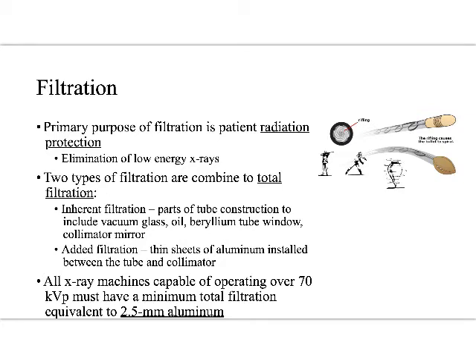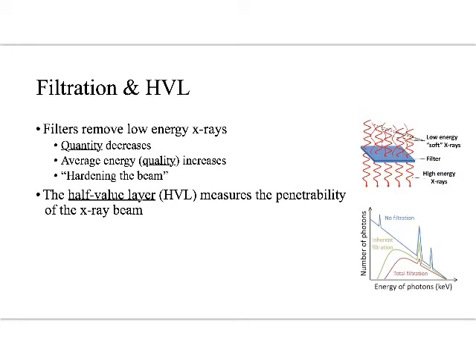Just memorize 2.5. Every diagnostic x-ray machine you will ever operate — unless you change careers and become a dental hygienist — has to have 2.5 millimeters aluminum equivalent. That goes back to characteristic x-ray production and what we know about how these x-ray tubes function.